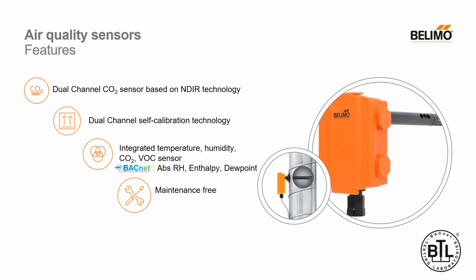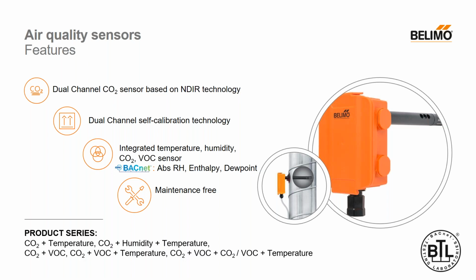NDIR technology is non-dispersive infrared technology. What it does is it only absorbs the gas that it's sensing, so it keeps the sensor very accurate, prevents any drift, and simply prolongs the life of the sensor because it's not sensing gases it's not looking for. Again, we have combination sensors, so you can get integrated VOC, CO2, temp, and humidity. They're low maintenance or maintenance free. And as you can see, it's a pretty wide range of combo sensors.